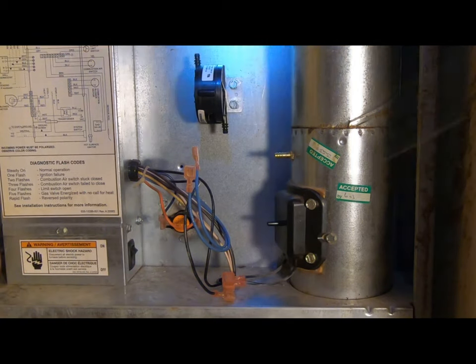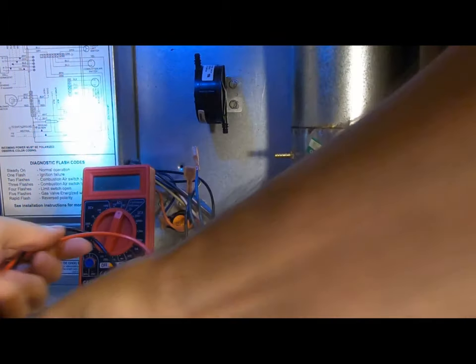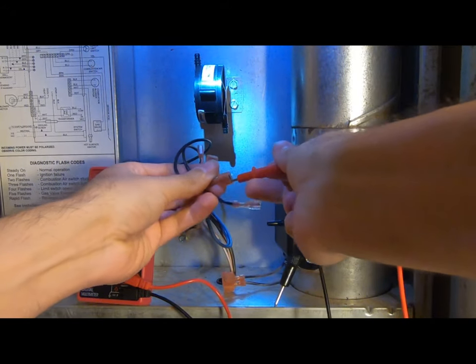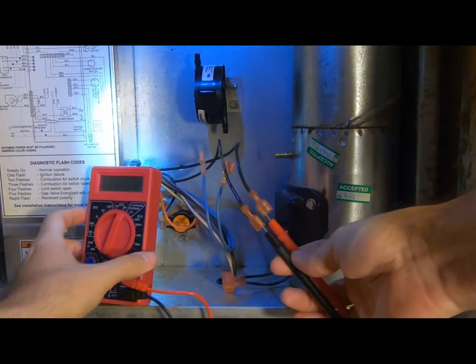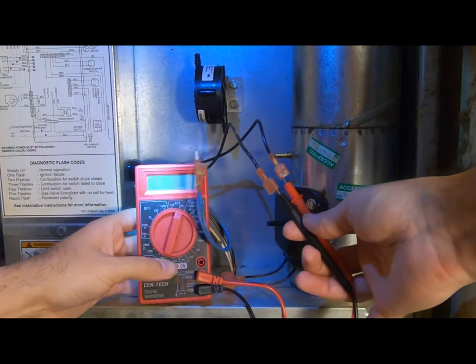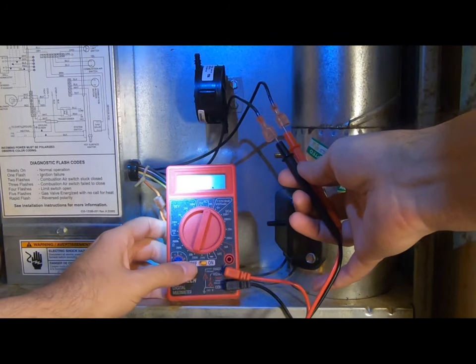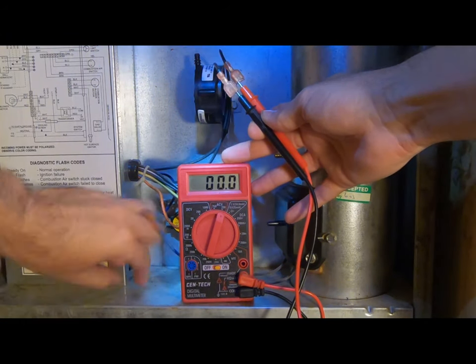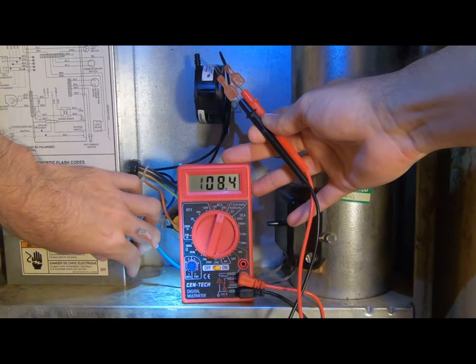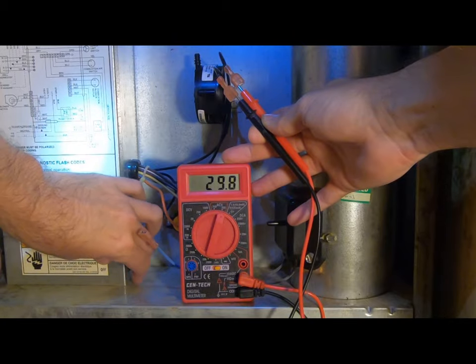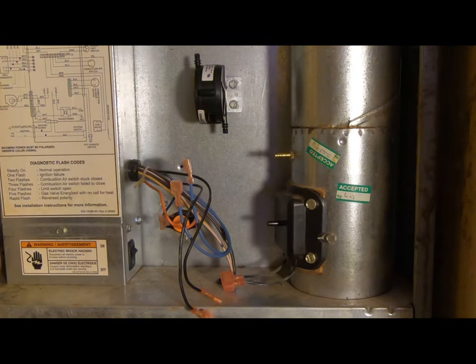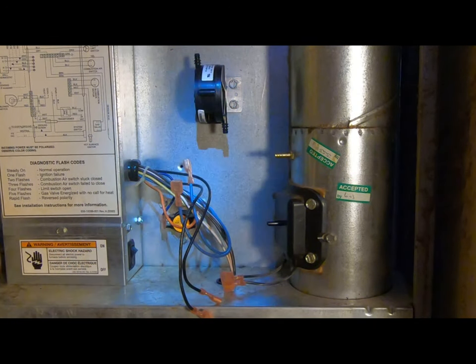But just to double check, just to make sure it was getting power, we'll get out our trusty somewhat abused meter and stick a probe in each of these suckers. Turn it on of course. So here we're showing basically zero. We turn it on. Shazam, 120 volts. So it is sending power to that motor, it is trying to utilize that motor, but the motor is not working.